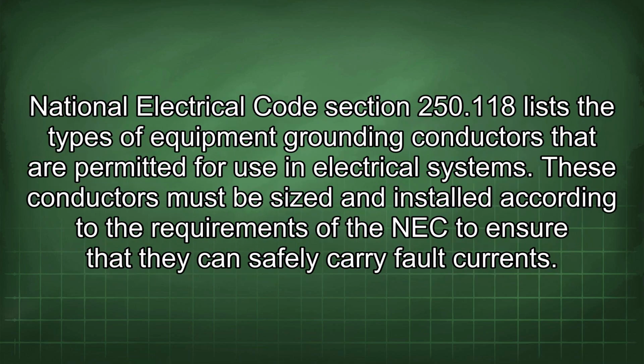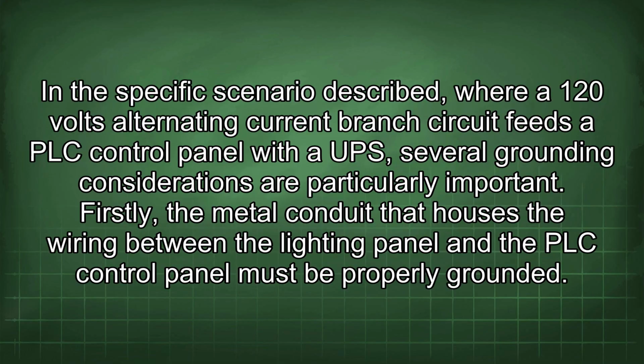National Electrical Code Section 250.118 lists the types of equipment grounding conductors that are permitted for use in electrical systems. These conductors must be sized and installed according to the requirements of the NEC to ensure that they can safely carry fault current. In this specific scenario described, where a 120 volts alternating current branch circuit feeds a PLC control panel with a UPS, several grounding considerations are particularly important.